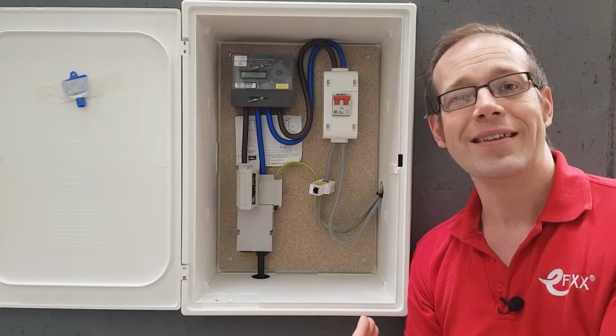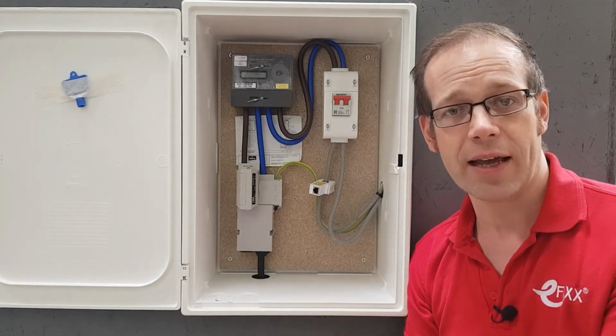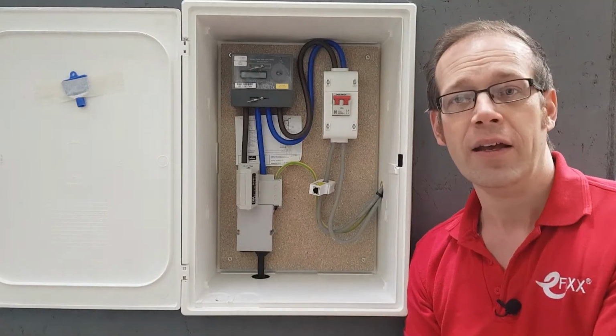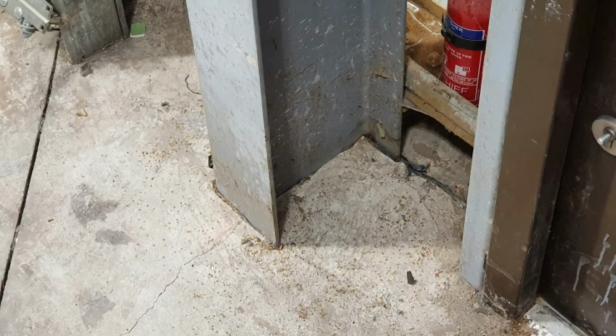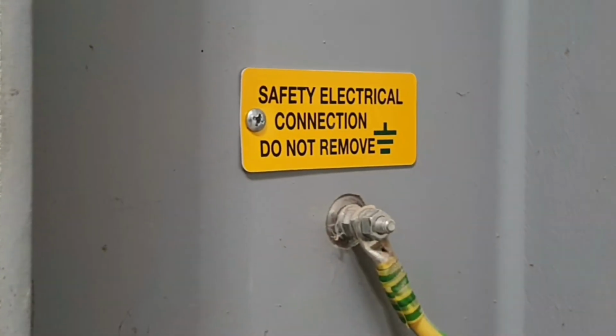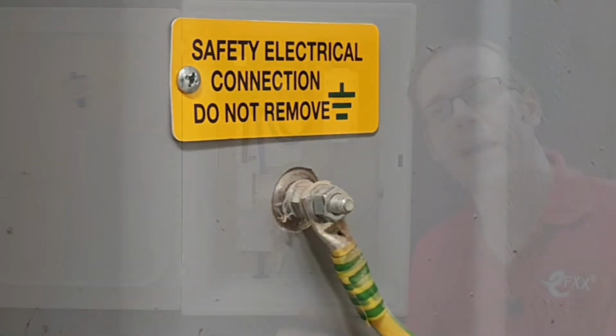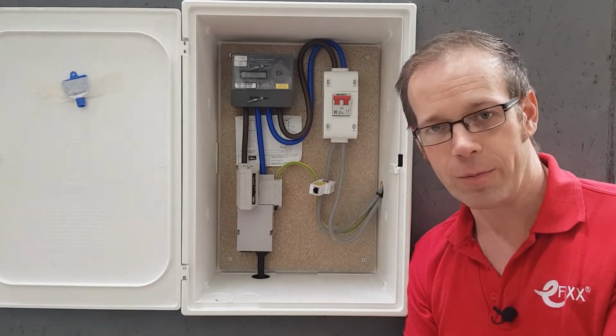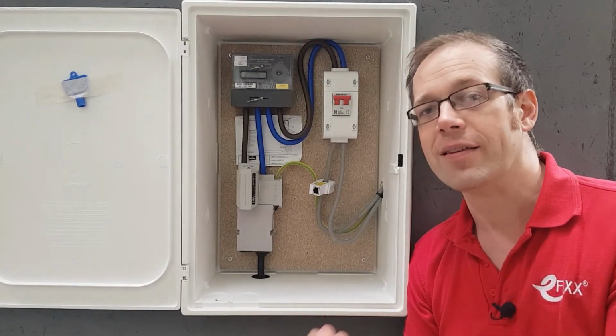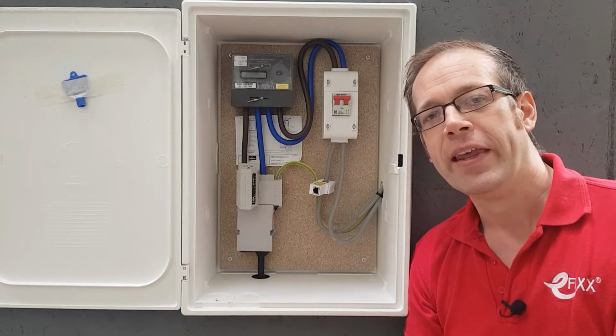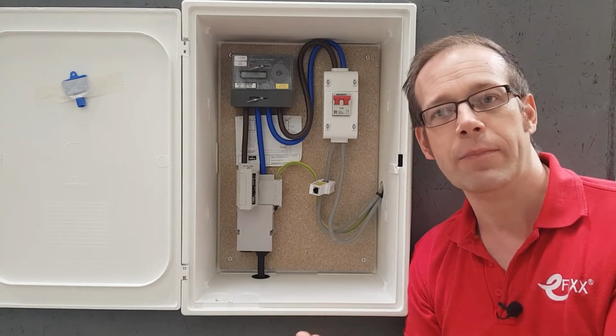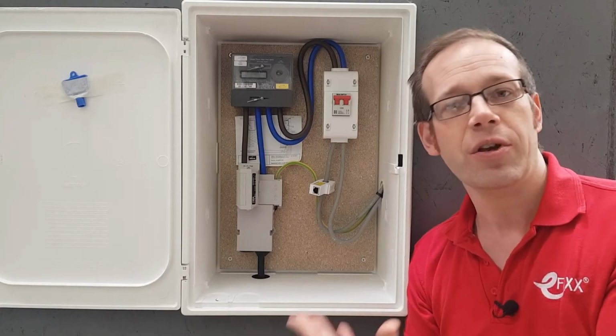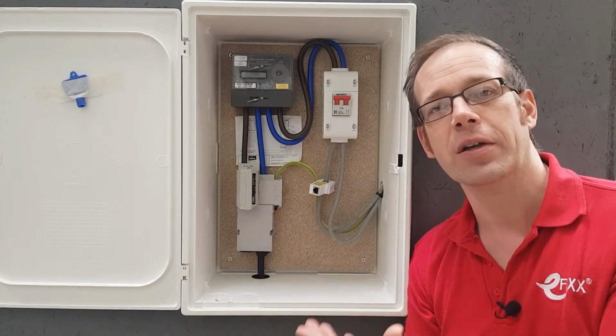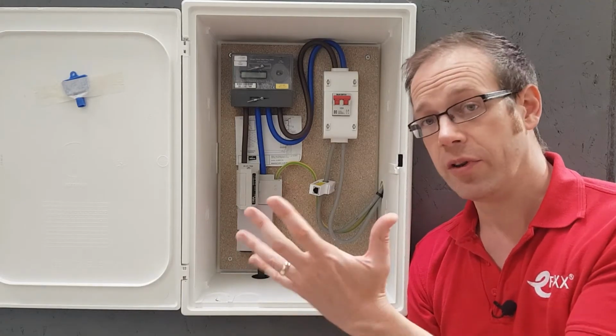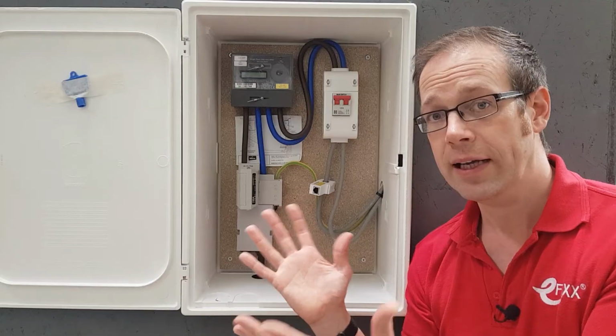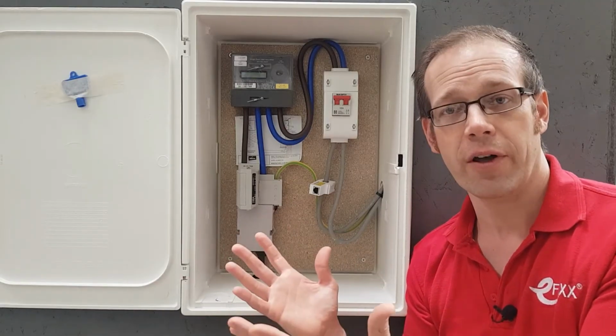Inside a property, the only place that this is likely to happen is if you touch a metal object that has a good connection to the literal earth, like say an incoming water or gas pipe or a piece of structural steel that is embedded into the ground. And that's why we connect these items to the main earthing terminal of a property via a bonding cable. It's not in case the pipes become live, it's to make sure that they do become live in this type of event. If every piece of metalwork that can be touched at the same time becomes live at 230 volts, then there's no difference in voltage between them and you can't get a shock if you touch them. So if I have 230 volts in my left hand and 230 volts in my right hand, there's 0 volts difference between them, hence no current flow and no shock.